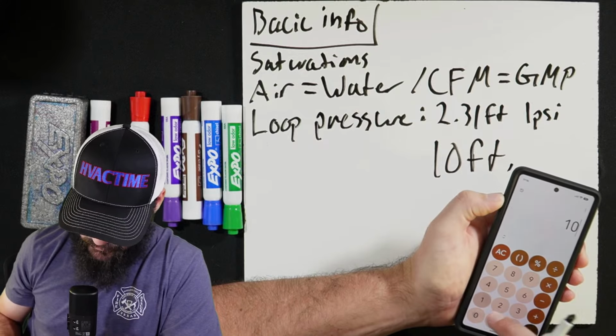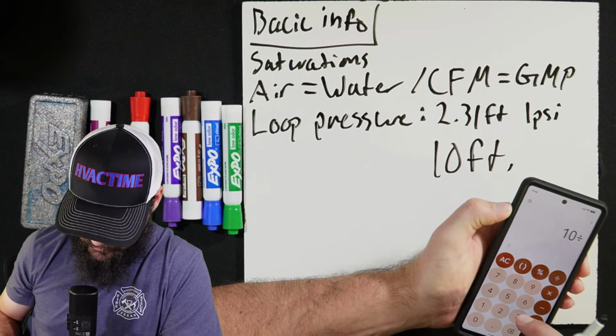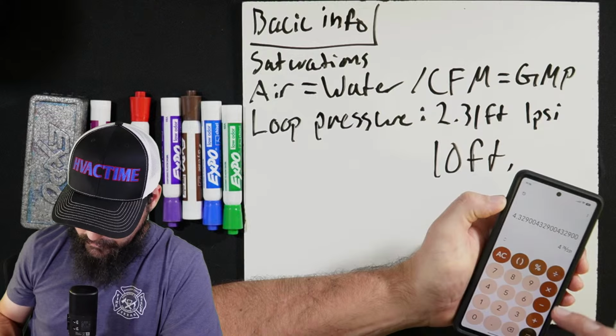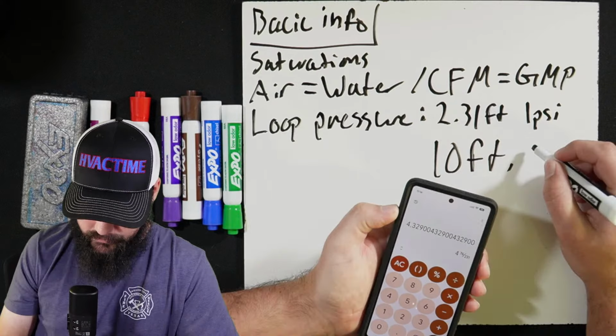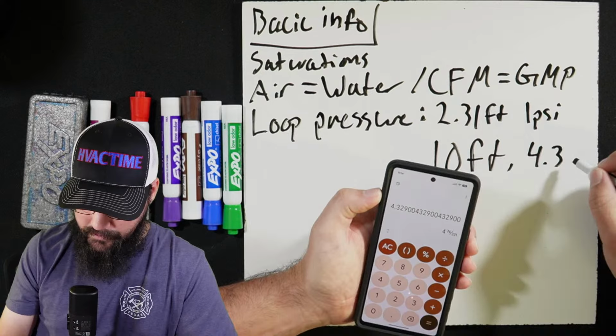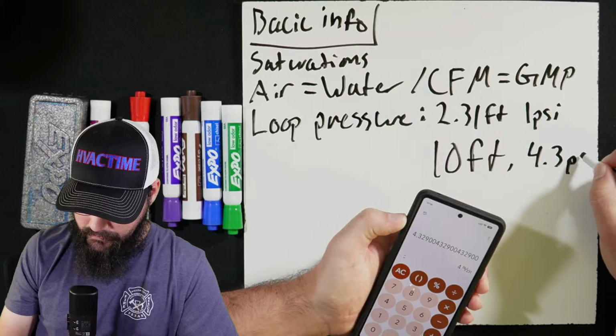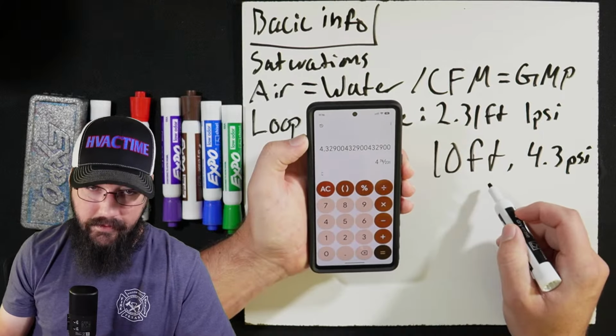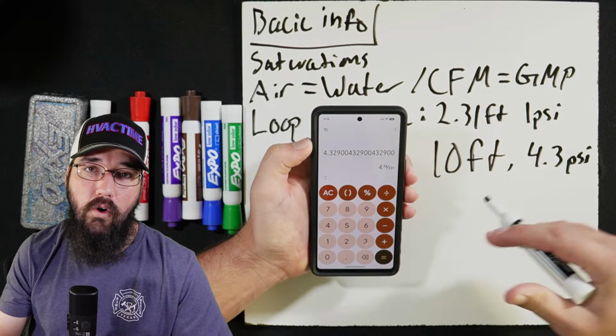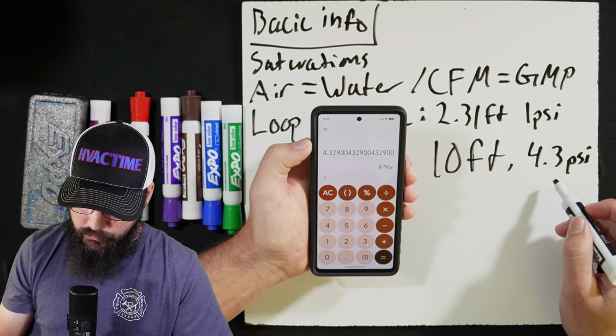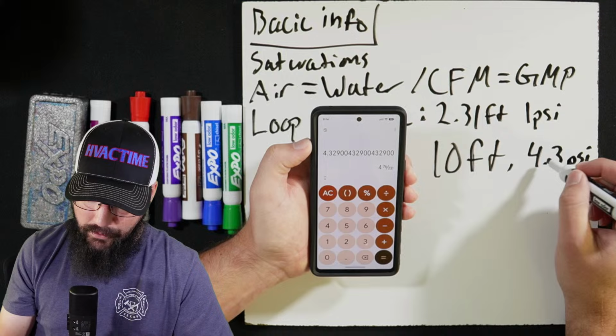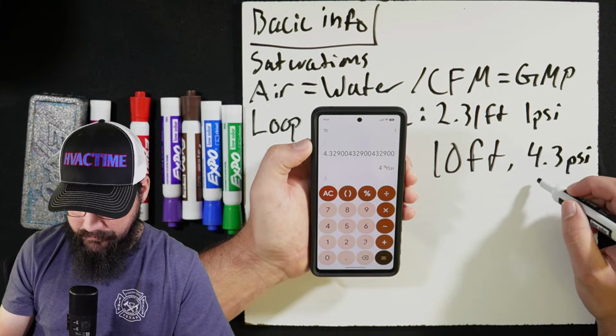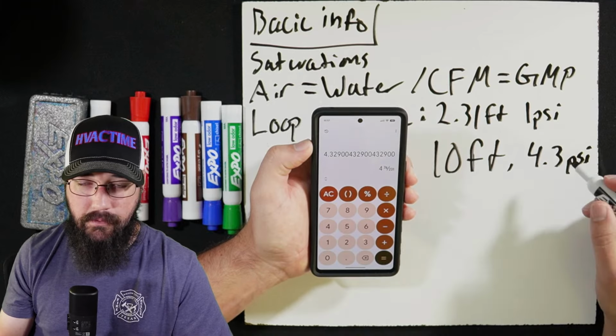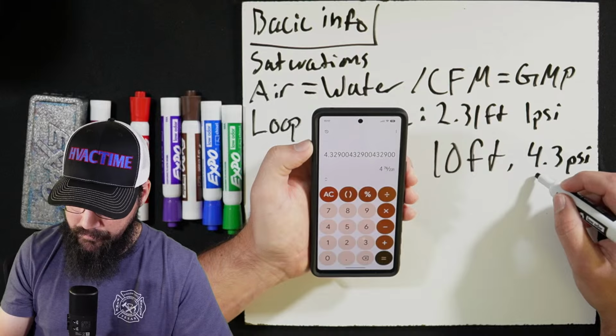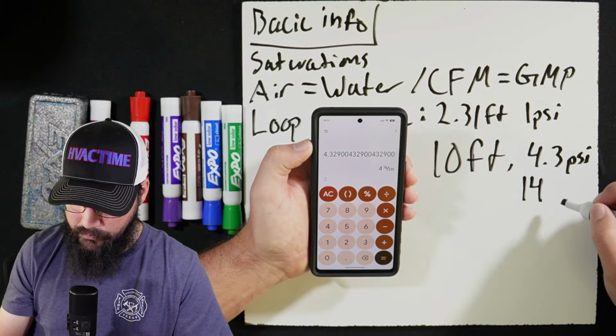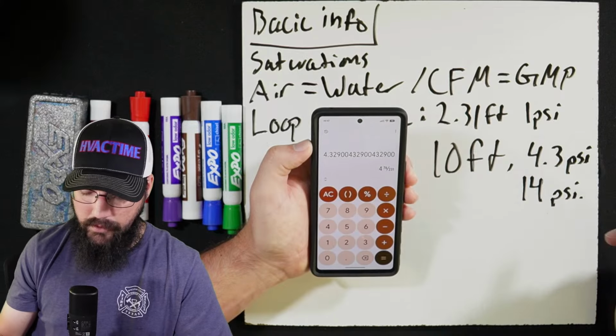All right, so 10, we're going to divide that by 2.31. Yeah, so 4.3 psi for a 10-foot tall loop height, right? So then I would add probably about 10 psi to that. Now this is all going to be on the suction pipe, for example. So then that would kind of turn into, I would just round to a 14 psi pressure target, right?